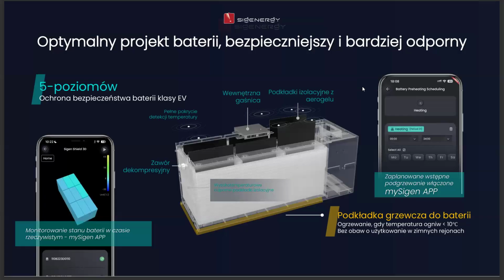2. Sigen Shield, Multi-Layer Cell Protection. Sigen is not just a battery in a box. Each battery module is designed as a multi-layer safety system. Why? Cell level detection. Every single cell has its own temperature sensor. We do not measure temperature somewhere inside the enclosure, we monitor each cell individually.